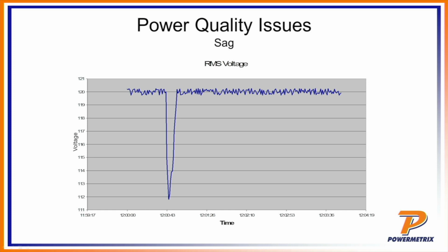That short of a perturbation normally would not be noticed unless you had a really sensitive piece of equipment, in terms of the meter averaging it. And so as such, it's just going to see that blip and move right on without even thinking about it. If you think about the meter this way, how often do we go out and read our meters? In the conventional sense, it's usually once a month, every 30 days. And so if I've got a perturbation that's lasting only a few tenths of a second, the meter's going to average that, and there's not really going to be an issue at all in your bill.